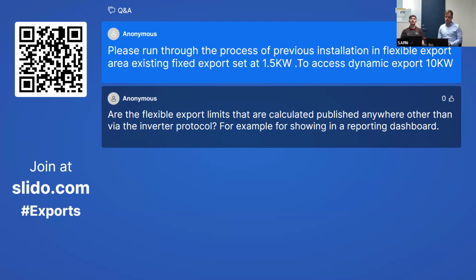Essentially, if you previously signed up for a fixed export of 1.5 because your equipment wasn't compatible during the trial period, and now want to swap to flexible exports, if the equipment is compatible you just need to raise a new application through Smart Apply and update the exporting plan. This involves adding your flexible connection, and the export monitoring device should already be on site. So it's basically updating the export plan and adding the flexible connection through Smart Apply, then registering the device and commissioning in Smart Install, followed by the capability test if you are swapping to flexible exports.